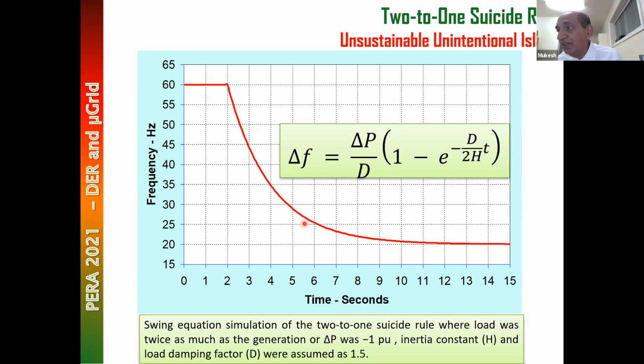When you work for 15, 20 years, people forget about basic things. They say, okay, what about 2:1? What about 3:1? So that required some convincing of colleagues about the 2:1 rule. The 2:1 rule basically assures, even with the load damping... Load damping is an effect where, if you have an induction motor and the frequency drops, the load of the induction motor also drops. That's called load damping. The point we are trying to make is that if the load is twice the generation, you are guaranteed to kill the generation. That's all the point I'm trying to make.